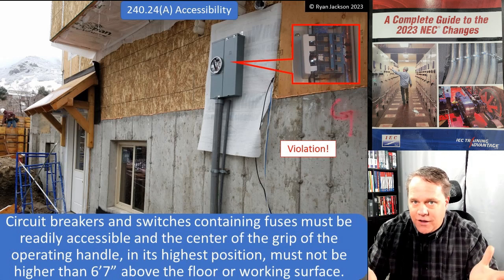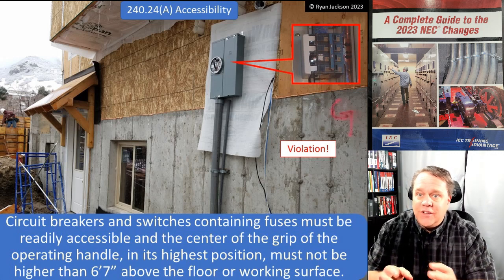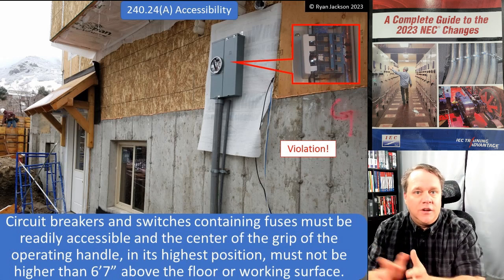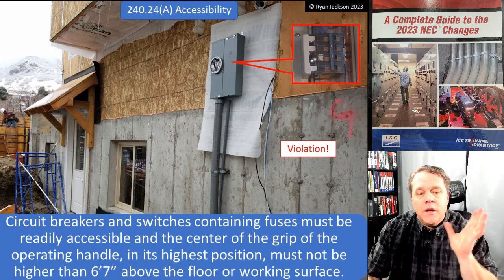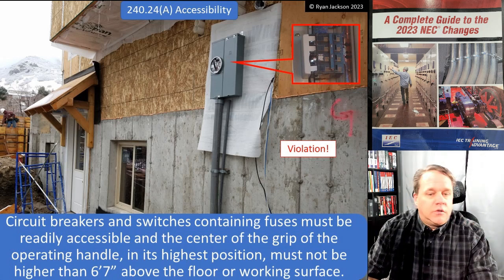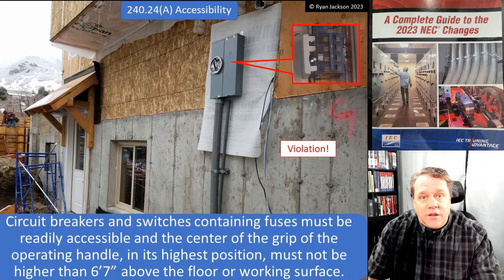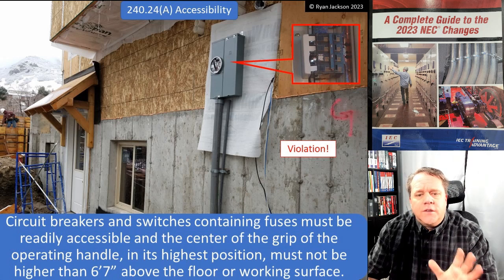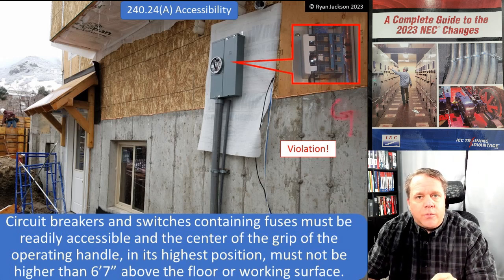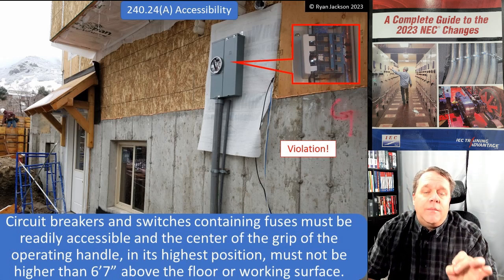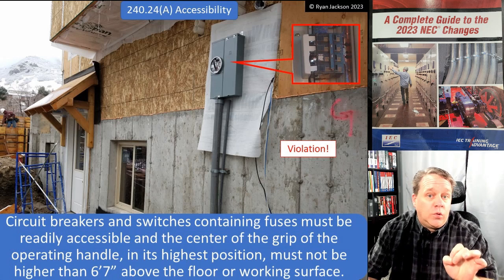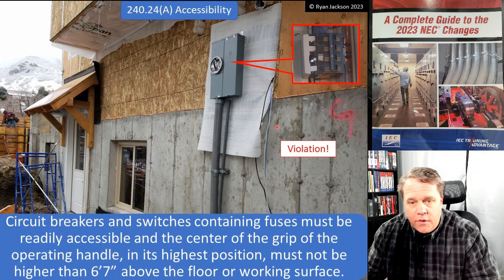We didn't really have any good exceptions here until the 2023 edition. Breakers and fuses have to be readily accessible, and the center of the grip of the operating handle in its highest position must not be higher than six foot seven above the floor or working surface.